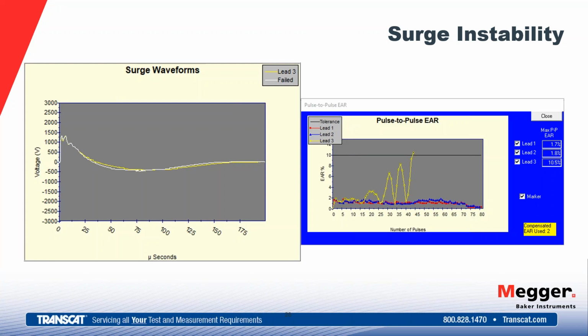So here we get an example of a surge waveform on the left. Yellow is the good waveform. The very next pulse actually caused the inductance of that system to go down, shifting the waveform to the left. So the white waveform is that failed waveform. And we're going to quantify how much it shifted here in our pulse-to-pulse EAR. As we see this activity here, that's an indication that we've got a weak turn-to-turn insulation.